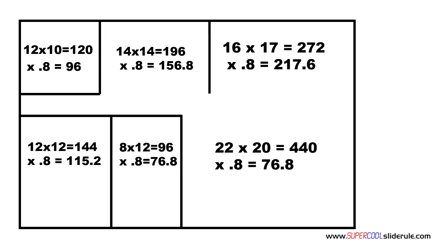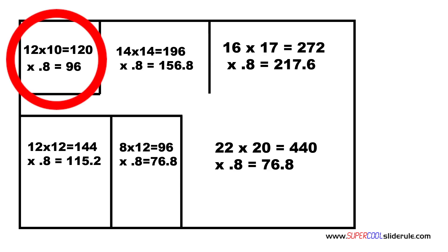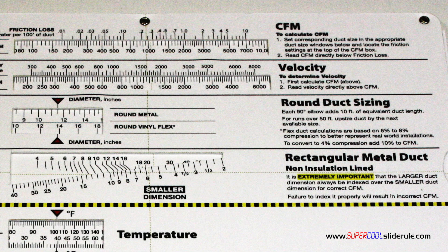In room one, the requirement was 96 CFMs. There are many ways to use the super cool tool, but the easiest is to index the required CFM directly under the .1 friction loss, which is also referred to as static pressure.